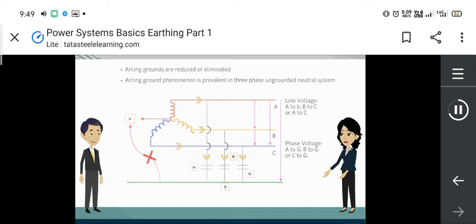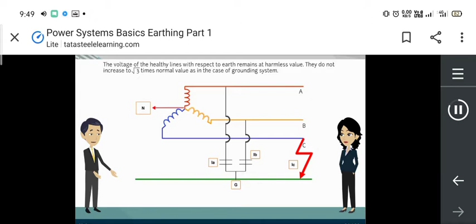So let us now consider that a line to ground fault has occurred near phase C. The charging current from A and B, that is IA and IB to the ground remains the same. The charging current is the summation of IA and IB. Now the fault current IC connects directly to the ground and hence feeds a high magnitude of current. Because of increased current, capacitive current in IA and IB will increase and lead to arcing in these two capacitances.